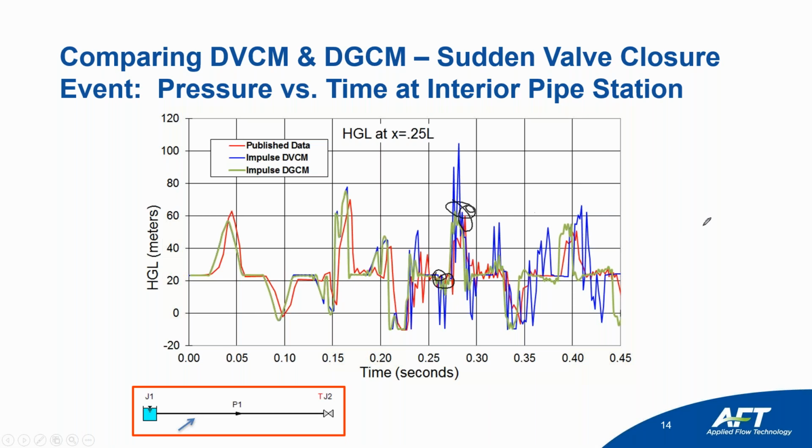And if the magnitude of those pressure spikes are relatively close, then that can serve as validation that maybe those are a bit more realistic. Again, you need to focus on the overall trends themselves when you're modeling cavitation, not the exact values themselves.